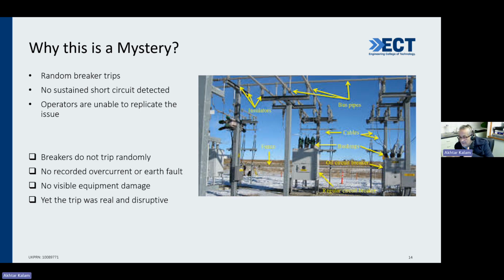Now, normally I would have asked you to answer these questions and work with me, but because of the time, it's only 1 hour, I'll give my own answers and let you ponder over the question itself. Because I want you to be curious. I want you to see your skepticism. Why did the breaker operate? Because in fact, breakers do not trip randomly. A breaker will only trip when the signal comes from the protection. As I told you, there was no recorded overcurrent or earth fault. There was no visible equipment damage, yet the trip was real and it disrupted the system.